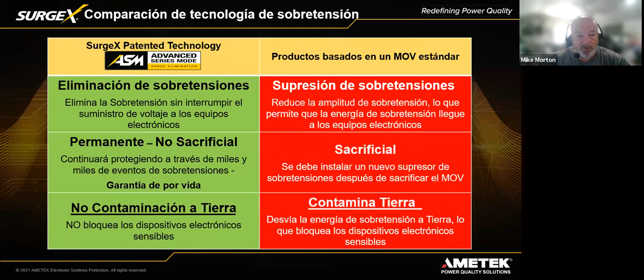This is the total advanced series mode protection. As you can see, it starts with the reactor, which is the first where the incoming power comes in. It will come in and actually exit this area and go directly to the secondary portion. But if you'll notice, the ground wire goes directly to chassis and it's nowhere involved in the circuit. And again, the reason we don't want it to be is we don't want to contaminate ground any more than it already is.